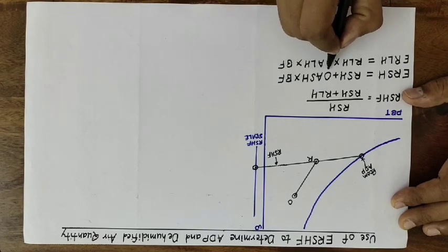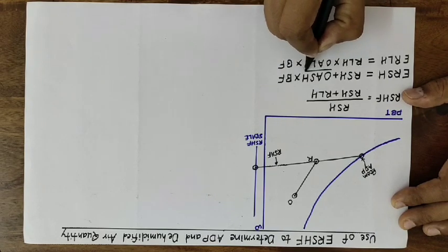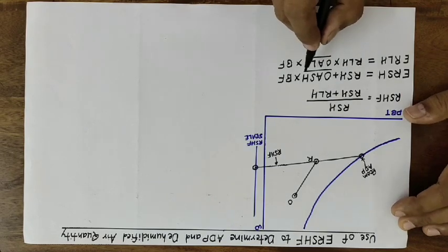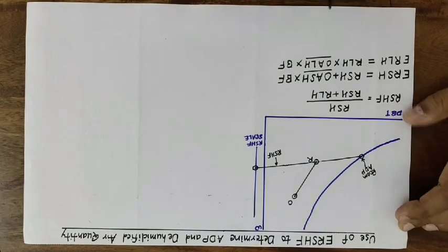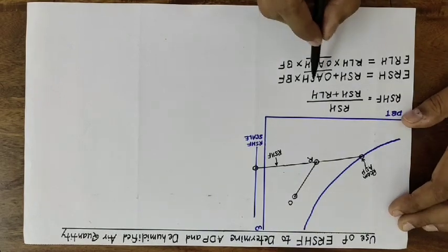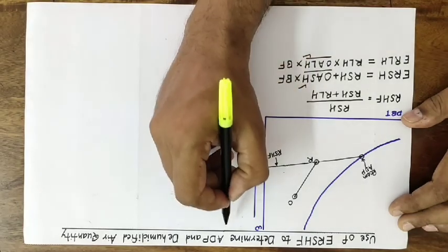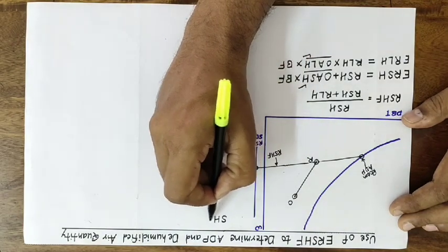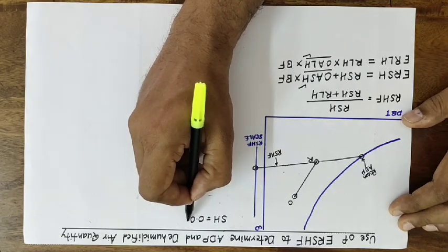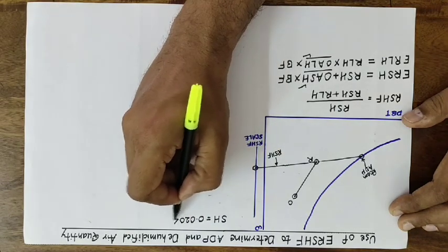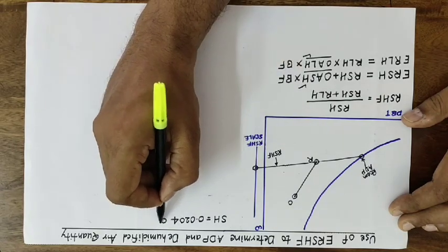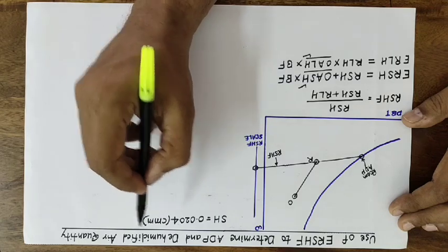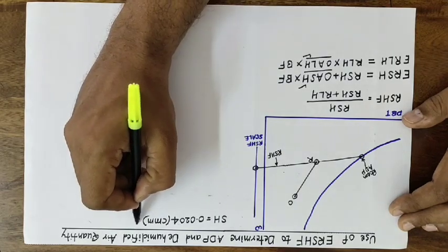The bypass factor of the coil must be known, and we must calculate the outside air sensible heat as well as outside air latent heat. We have learned the sensible heat formula as 0.0204 — this is essentially the formula of ṁ × Cp of air, where the volume flow rate is taken in CMM (cubic meters per minute), divided by 60 to convert to cubic meters per second, multiplied by ΔT.